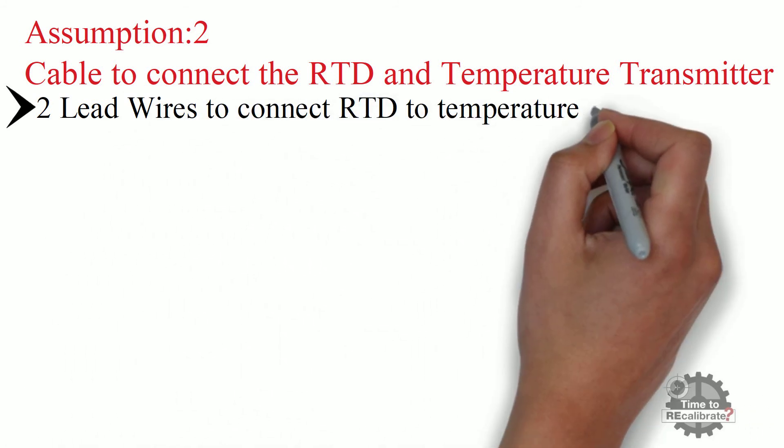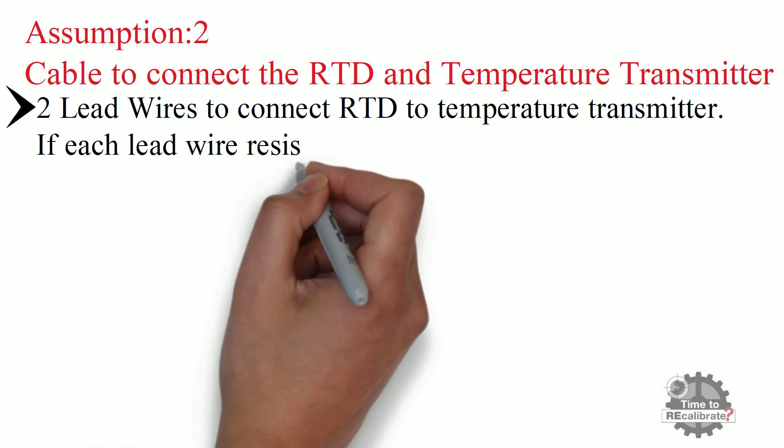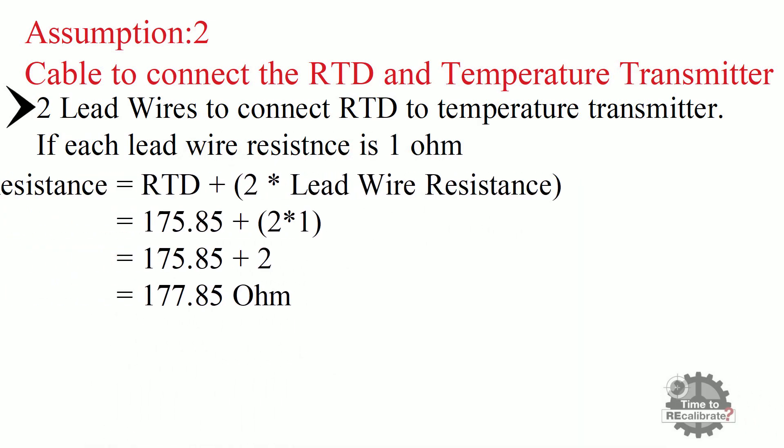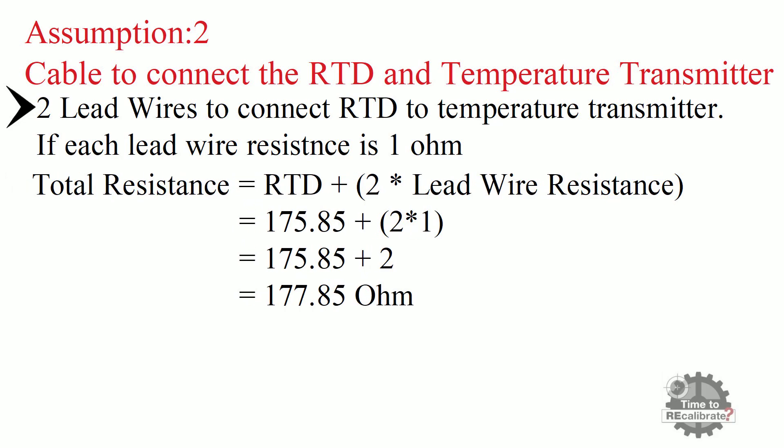For example, if we use two lead wires to connect RTD to temperature transmitter and if each lead wire resistance is 1 ohm, and if we put all these values in this equation, then we will get 177.85 ohm resistance value.